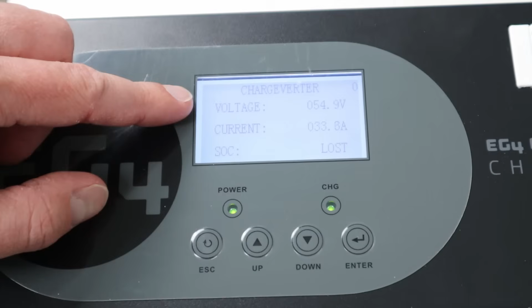So I've started the test and I'm powering the EG4 Chargeverter with the F3800's 240 volt output. If you look closer at the screen, you can see that we are pulling 2000 watts from the power station to charge the other power station. I have the voltage output set to 55 volts as the peak output, so we aren't able to get the full 50 amps, but we are getting about 33.5 amps peak.